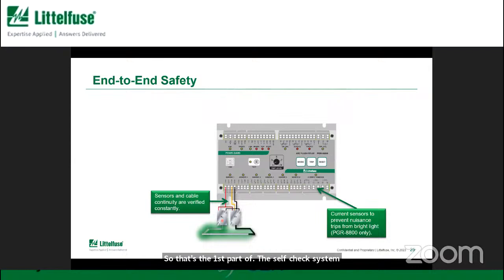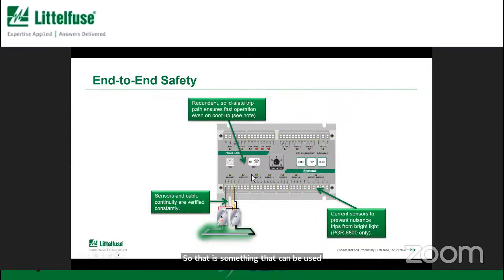The second is that the 8800, this one model, does have the ability to bring in current as well. So some customers have expressed some concern. What if we have somebody with a flashlight looking in the equipment? We commonly have people with lights, and we're worried about that triggering the arc flash relay. So if that is something that's a common occurrence, you can bring in current transformers and require light as well as increased current before you would let the relay trip. So that is something that can be used. Inside the relay itself, there is a backup circuit. So we have a regular microprocessor circuit as well as a solid state backup circuit. So there's a redundancy inside the hardware as well.